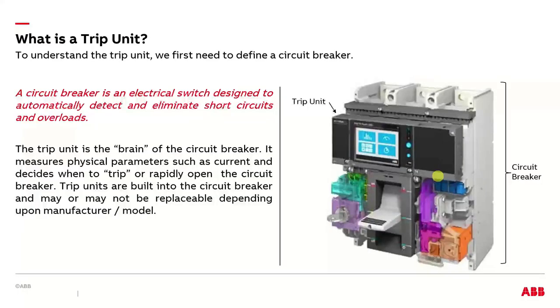Not a common term, but to understand what the trip unit is, we first have to define what we're talking about with a circuit breaker. So I think, and I came up with this definition, and hopefully it's good: a circuit breaker is an electrical switch designed to automatically detect and eliminate short circuits and overload. The key word there is automatically, and the automatically part is the trip unit, because without the trip unit, the breaker is just a switch, a heavy duty switch, but it's just a switch.